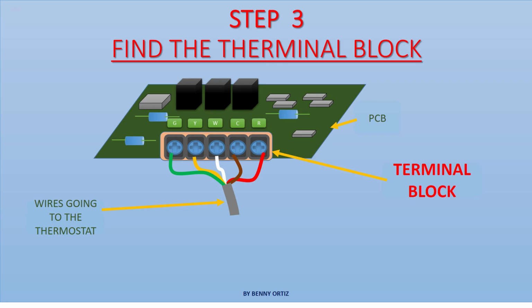First, make sure there is a common or C terminal on the terminal block. Check to see if there is a wire connected to it. If there is no wire connected to the C terminal, turn on the power and use a multimeter to measure the AC voltage between the C and the R terminal. If it shows 24 volts AC, that C terminal is active. This 24 volts AC could be approximately 27 volts AC RMS in unloaded condition.